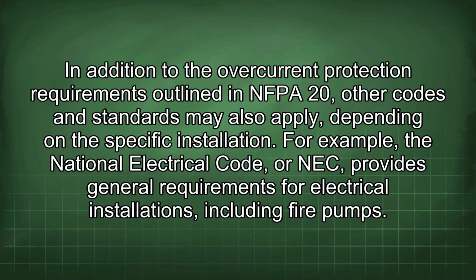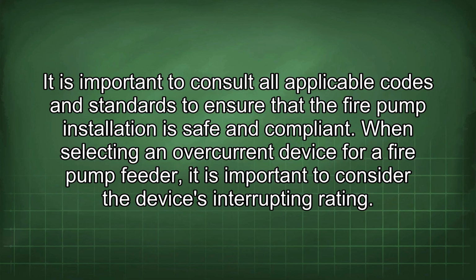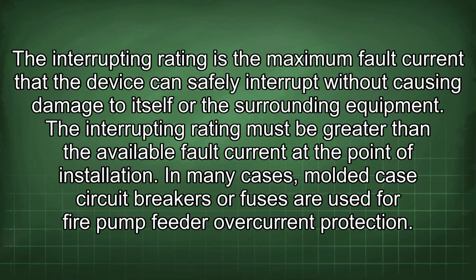In addition to the overcurrent protection requirements outlined in NFPA 20, other codes and standards may also apply depending on the specific installation. For example, the National Electrical Code, or NEC, provides general requirements for electrical installations, including fire pumps. It is important to consult all applicable codes and standards to ensure that the fire pump installation is safe and compliant. When selecting an overcurrent device for a fire pump feeder, it is important to consider the device's interrupting rating. The interrupting rating is the maximum fault current that the device can safely interrupt without causing damage to itself or the surrounding equipment. The interrupting rating must be greater than the available fault current at the point of installation.